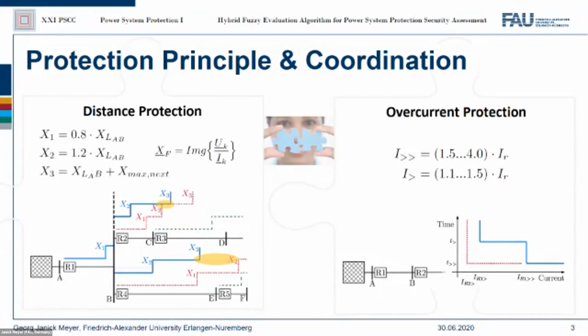Overcurrent protection relays are the most common relay types and are available with various timing characteristics to coordinate with other protection relays. The picture on the right side shows the grading chart for an overcurrent relay with 2 tripping stages. To prevent unselective tripping during normal operation, the overload stage must be higher than the highest load current that can occur. The short circuit stage depends, of course, on the short circuit level and must be coordinated also with subsequent relays. Okay, so far so good. Sounds like a simple task to coordinate both protection principles.